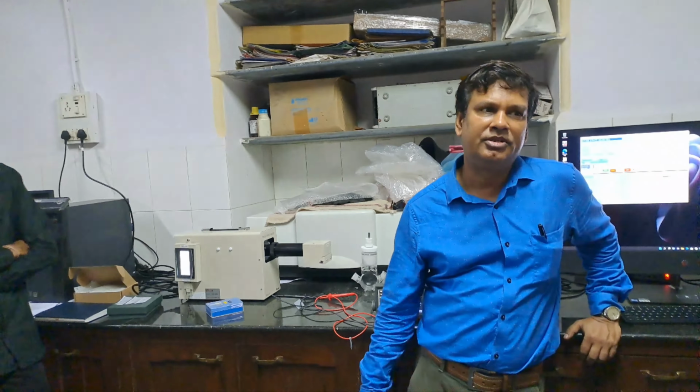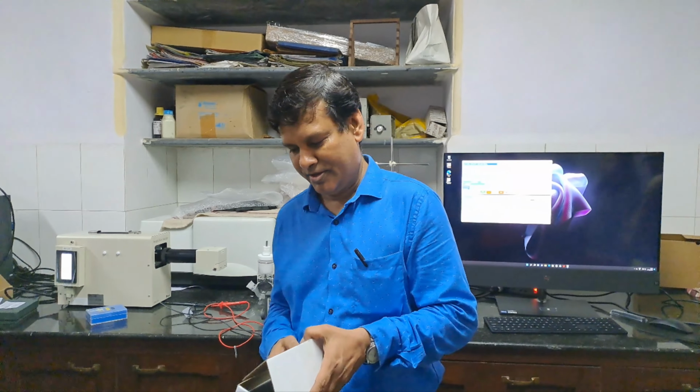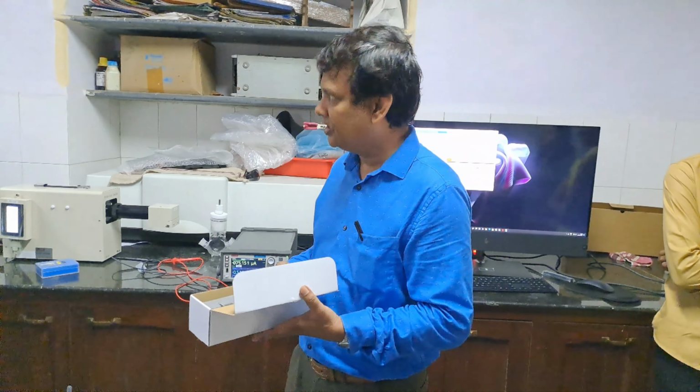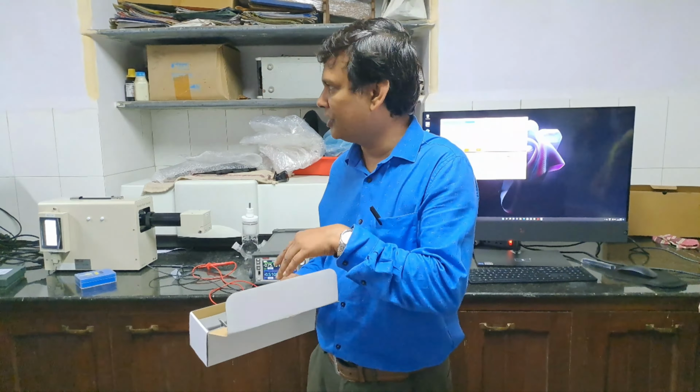Sir, does the instrument need some charges? Only the power supply. Can you zoom it back? See, this is the lamp which is inside. This takes power, and this is 150 volts. One has to handle it very carefully. No grease on the glass, and use it with gloves.